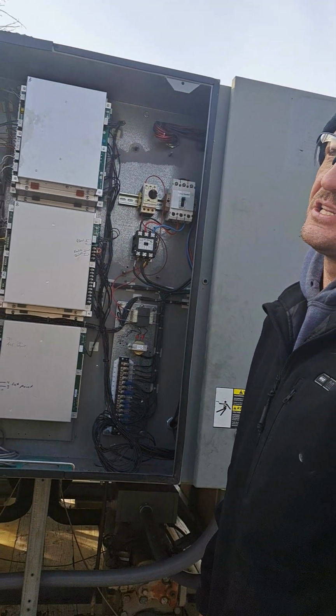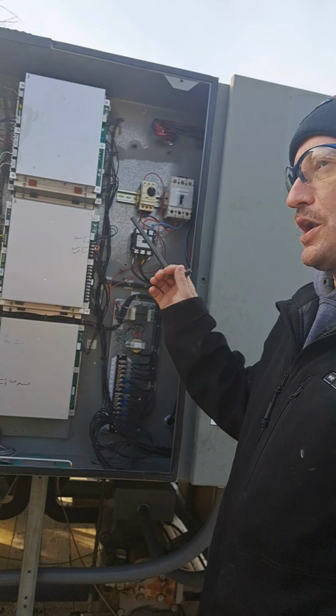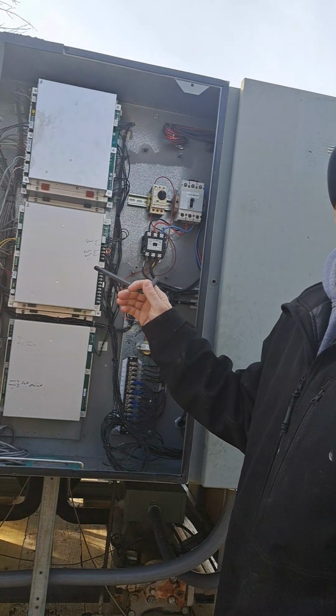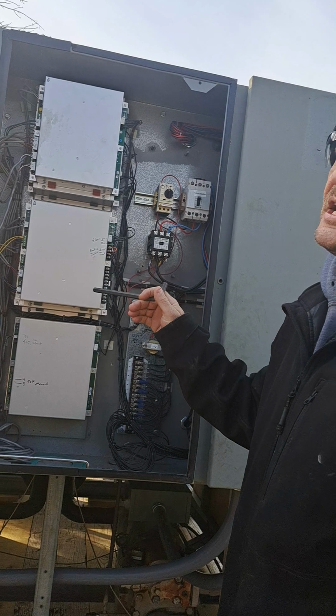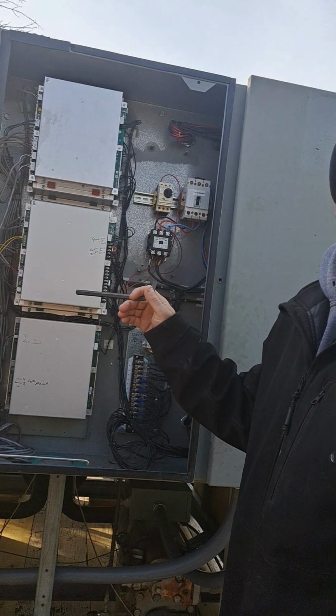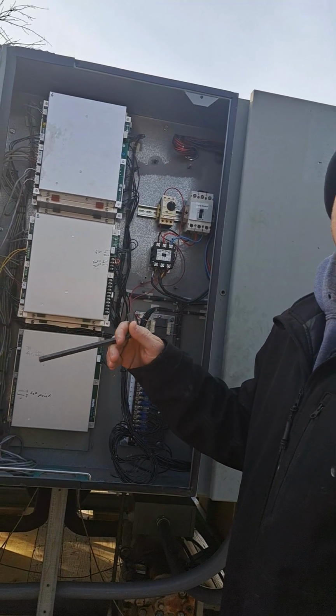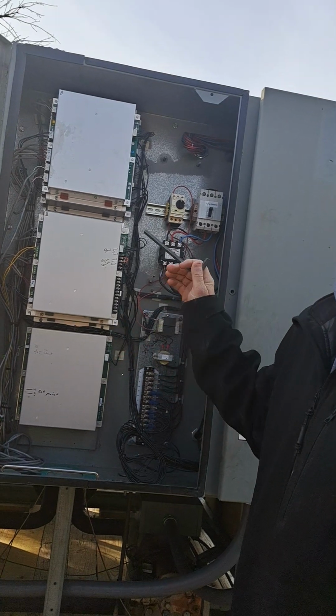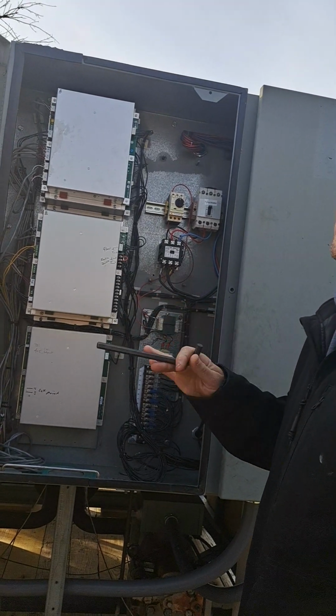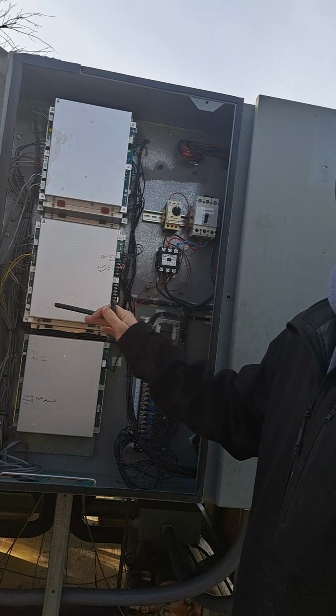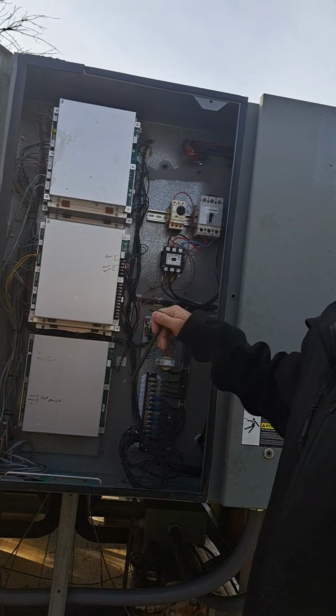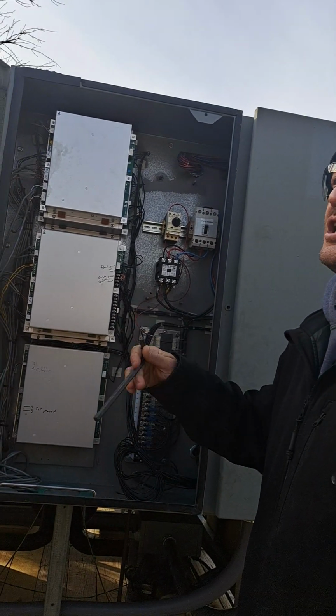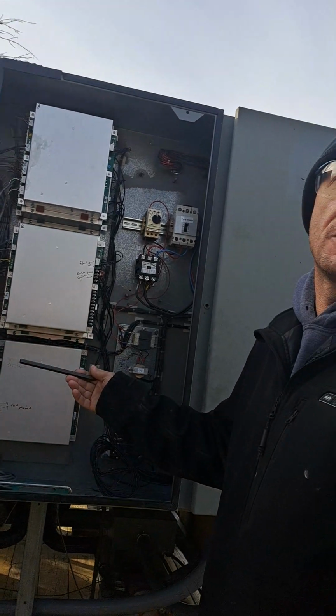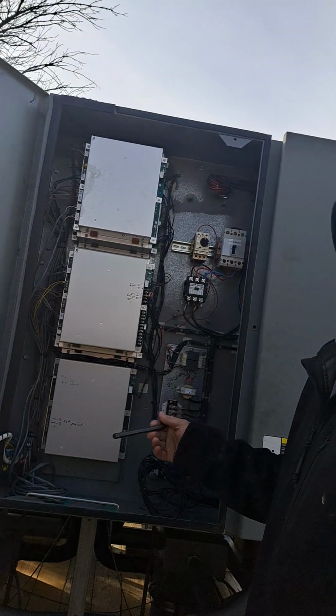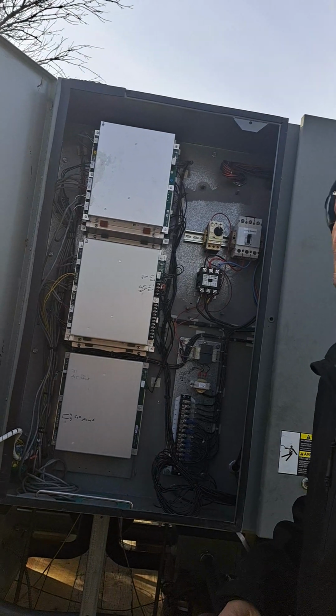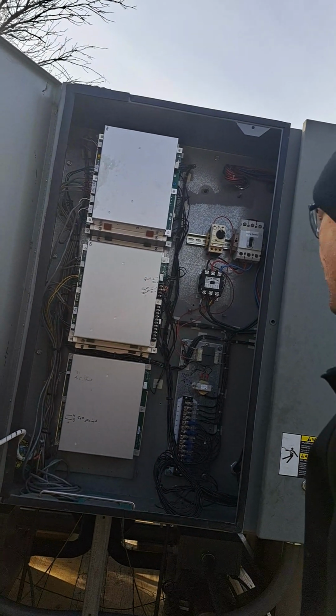Okay. So that's something that if you're gonna put a vent in that pipe next year, it would be a good idea to put like a 1.25 inch bushing in there, and then permanently install a flow switch, and you can get it wired up here. It's a good safety device to have, because if your pump shuts down, this thing has no way of knowing that. Right. And it'll continue to run the compressors, and it could actually freeze up and burst tubes, and then you're looking at a new chiller. Okay. So that's definitely something that'd be a good idea to add.